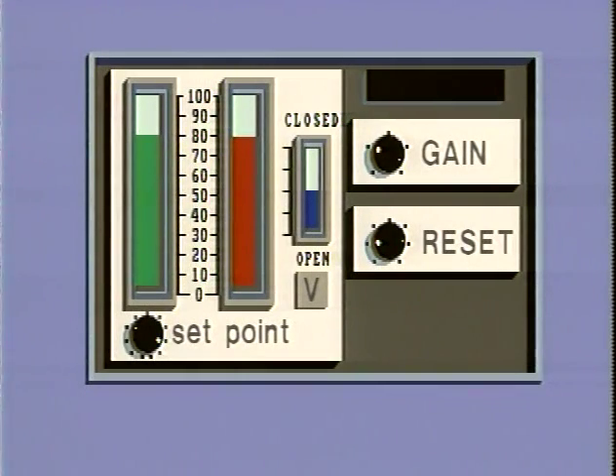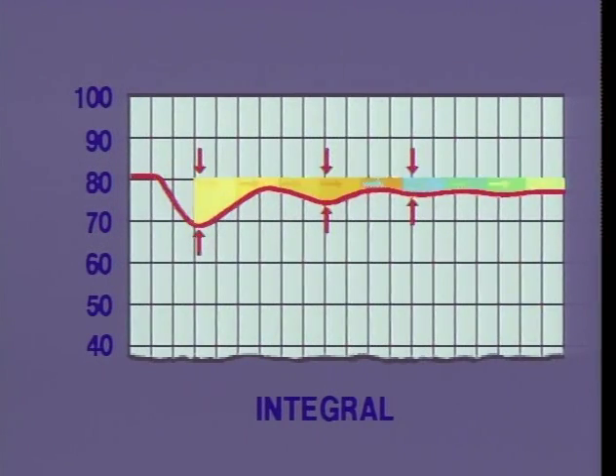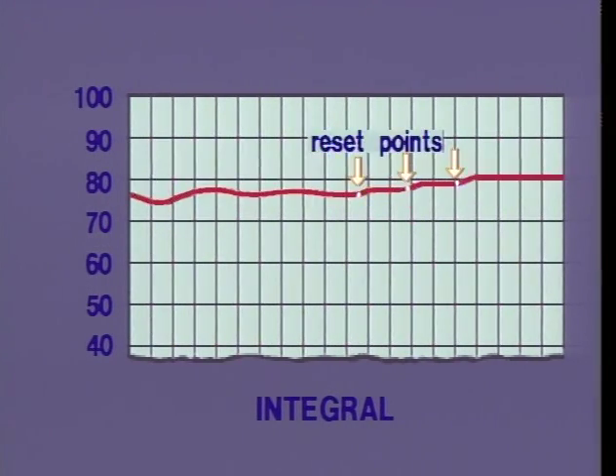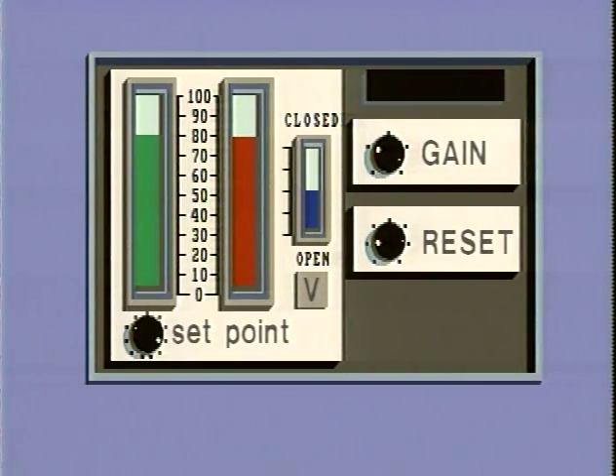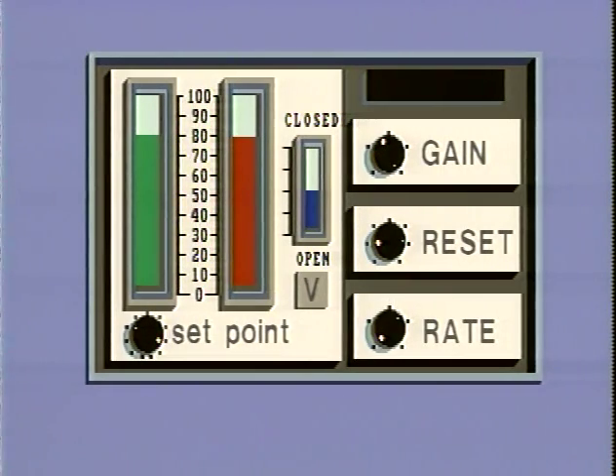An integral unit was then added to the controller. By responding to the duration of the temperature error, the integral unit detected that the error was still present sometime after the load change. The signals from the integral and proportional units combined to correct the error or offset. Although the proportional integral controller worked well to eliminate offsets, its output signal did not react quickly enough to reposition the valve during sudden load changes. Each time a bottling machine was started or stopped, some product was lost. A derivative control unit was then added to the controller. This unit could detect the rate of temperature change and cause additional valve movement whenever the temperature changed rapidly.